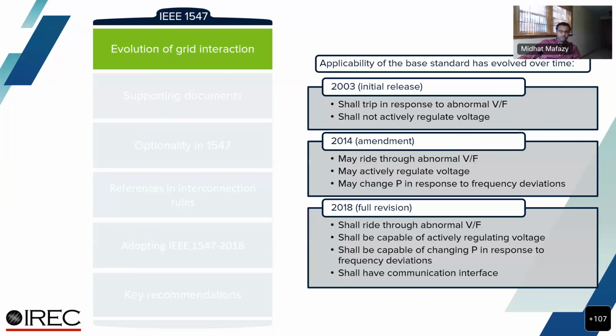By about 2012, it was becoming clear that DER, especially in the form of solar PV, were becoming a larger share of generation on the grid and needed to be relied upon during abnormal conditions. California was considering how to adapt smart inverters which could support the grid. 1547 was amended in 2014 to allow for greater ride-through capability and allowing for the DER to regulate voltage without requiring it. That is why you see the shift in language from shall trip, shall not regulate voltage to may ride through, may regulate voltage.